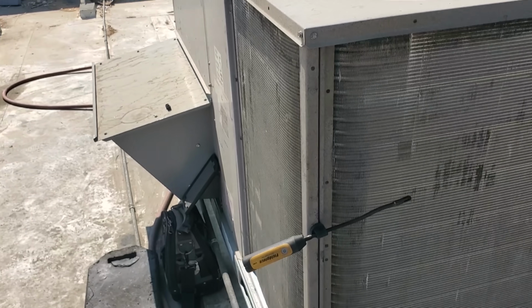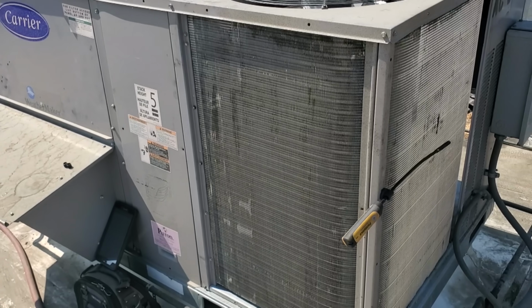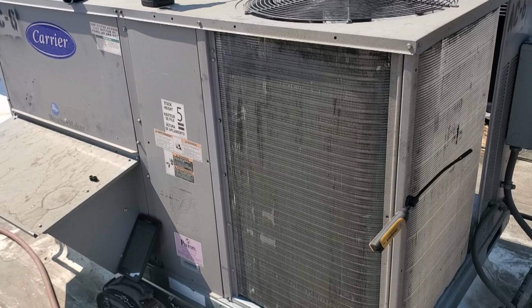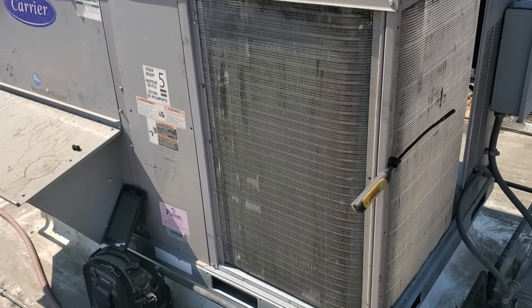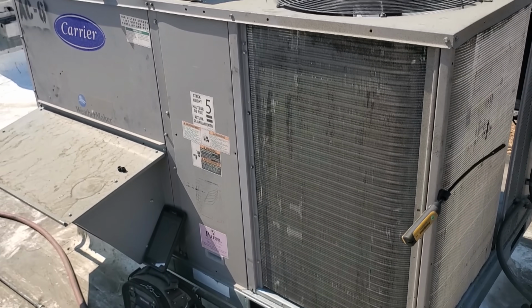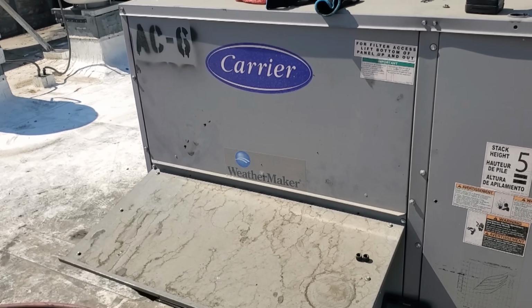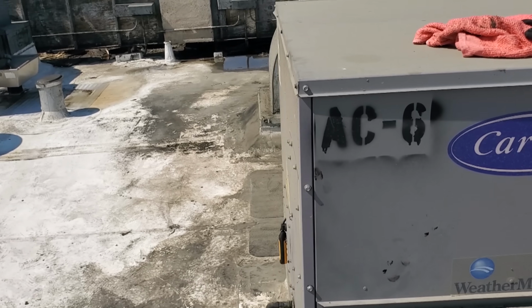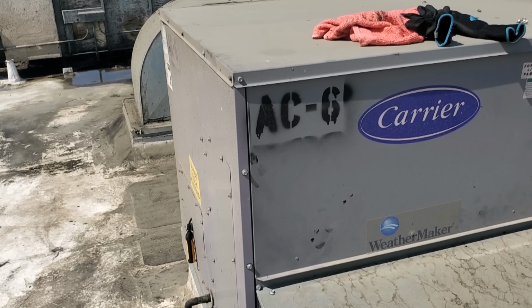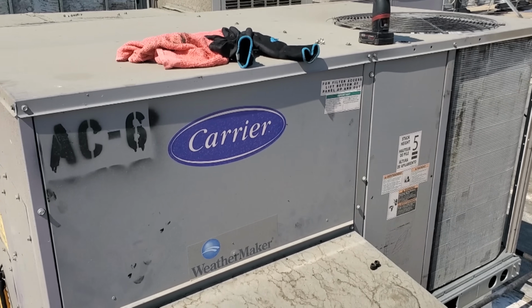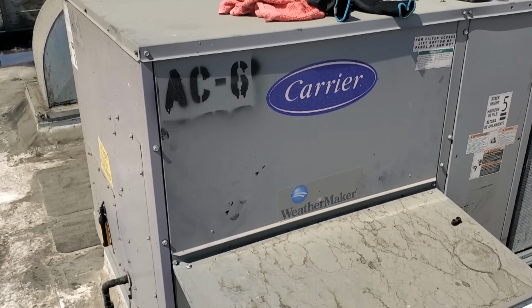I think it was just a faulty breaker. It wasn't tripped when I arrived, but the fact that we lost phases makes me think that it tripped and then it didn't reset. Everything's good. We cleaned it up as best as possible. This is one of those situations where you're never gonna win. I'd like them to replace that blower wheel, but I don't know if they will. It's not vibrating that bad. It's got a little bit of a vibration, but that's it. We're gonna wrap this one up.